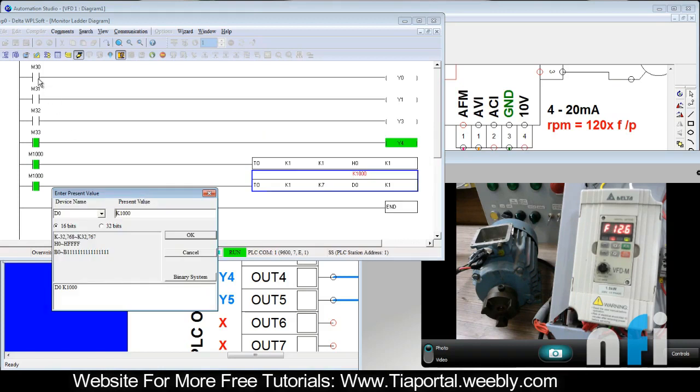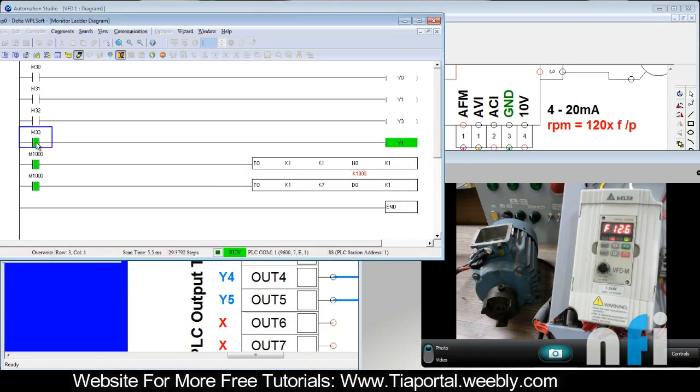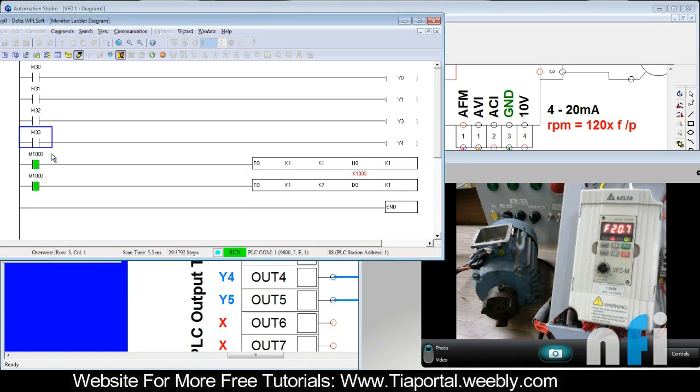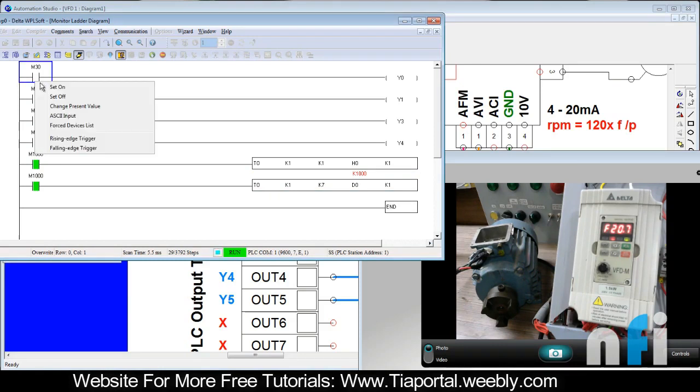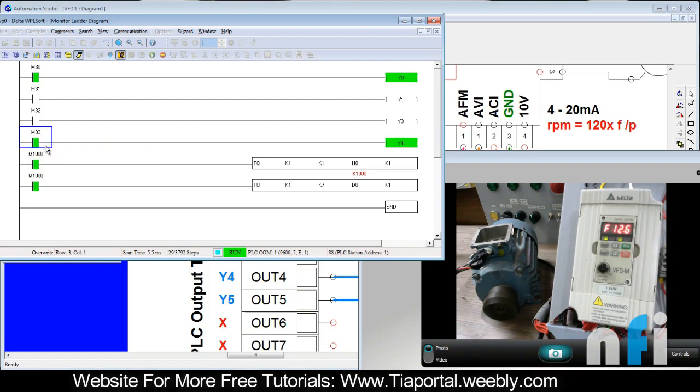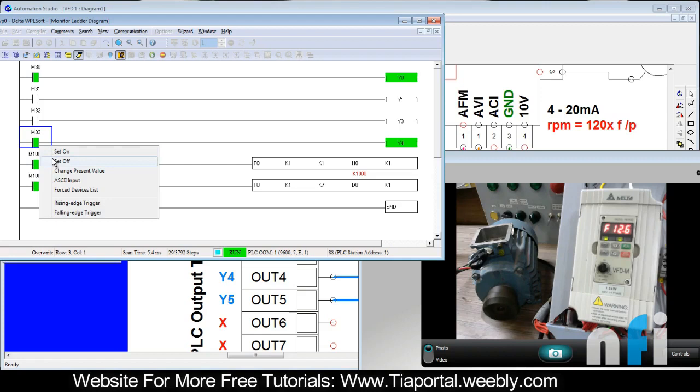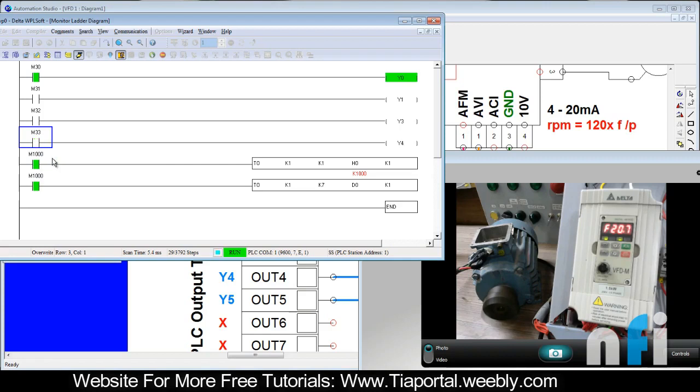Right now this is my second source. If I change D0 to K1000, frequency is changing. Now if I turn off M33, frequency will roll back to 20. So when you start the motor it will run at 20.7 Hz. If I select this one, frequency will jump to 12.6.